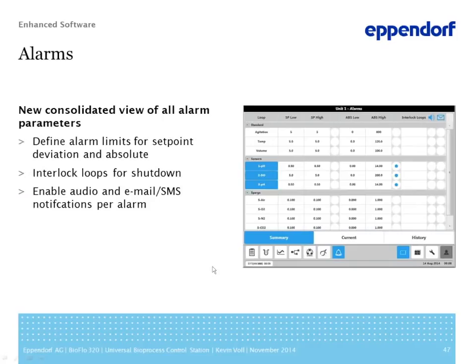Your alarm screen, this is where you would define the alarms. So as we've always done in Eppendorf and New Brunswick, we have set point based alarms, which are just deviations from a set point, and we have absolute alarms, which are really absolute thresholds that you never want to cross. Those are really the red alert alarms, and we now offer the ability to set all these alarms from a consolidated screen. You can interlock the loops that you need, so this is really typically used for if you have a high foam alarm in which you want to shut down agitation or airflow to protect a filter.